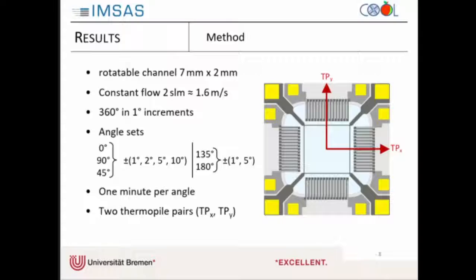And for the measurement, we need an angle set because we do not want to measure all the 360 degrees. That would take too much time. And we know from further measurements that there are some critical angles. And the critical angles are the 0 and the 90 degree, and the angle of 45 degree in the middle. And to analyze them, we make a subset of angles of plus minus 1, 2, 5, and 10 degrees, and so we can analyze this critical angle. And there are 2 other angles we want to analyze. It's 135 and 180 degrees. And we have a smaller set of sub-angles of plus minus 1 and 5 degrees to analyze them. And we measure 1 minute per angle. And this is around about 300 measuring points per each angle.